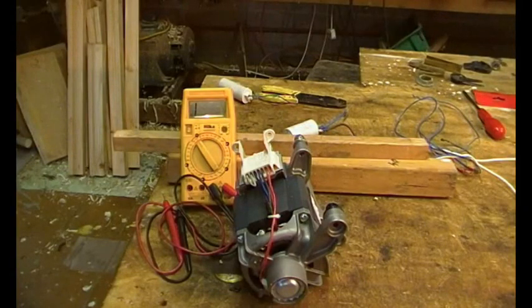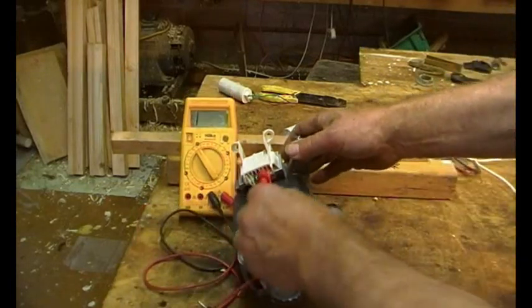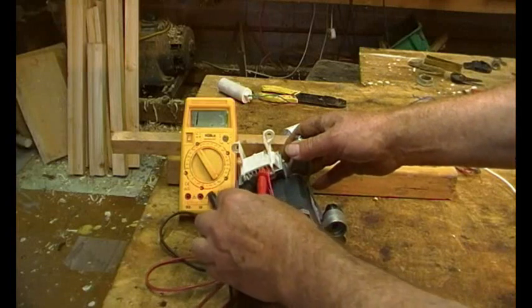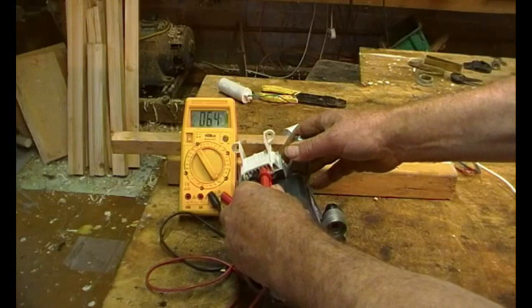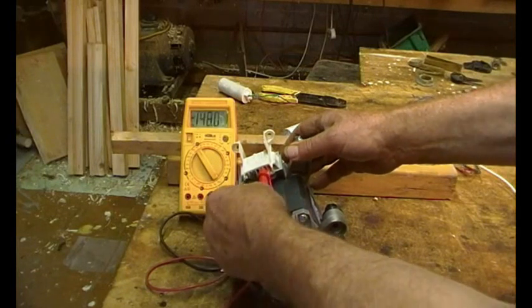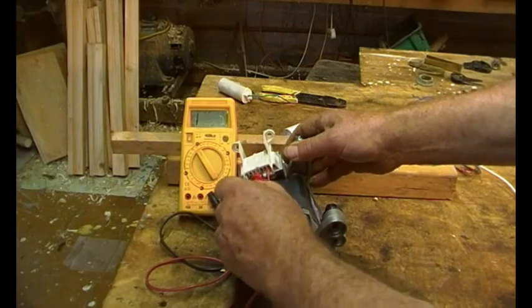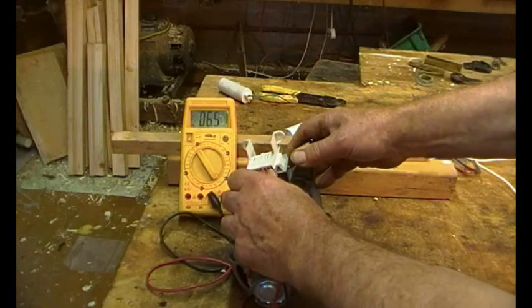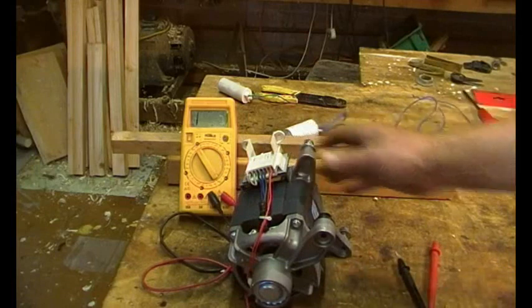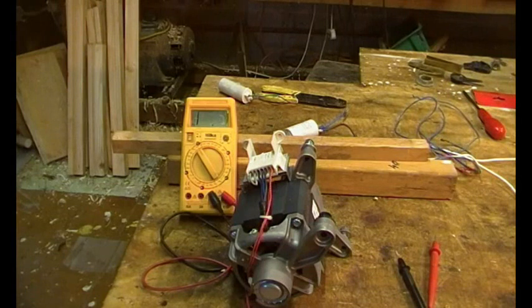But those three wires there are the three phases. So I'm assuming the first thing to do is to check that all three sets of coils are the same resistance. That's the plan. So we've got the meter set on 200 ohms.